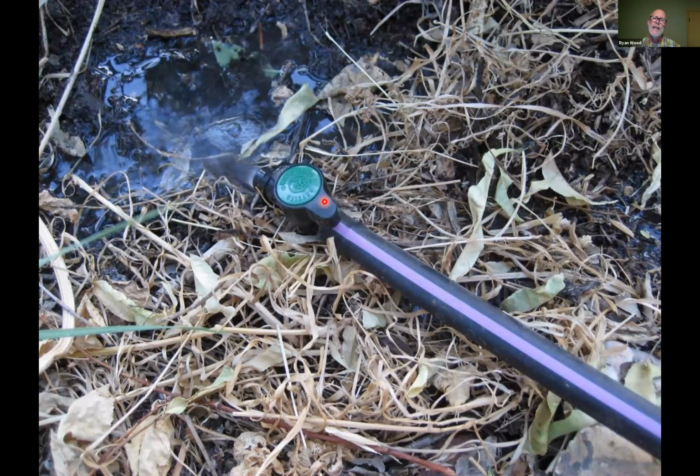And then depending on your laundry machine, you're going to have at least 4 to 12 outlets. It's going to depend on how big a drain hose you have on your washing machine. For example, if it's a 1 inch diameter hose coming off your washing machine, you're going to want at least six half inch outlets, because if you do the math on the inside diameter, those 6 outlets are going to be the equivalent of a 1 inch diameter hose. We don't want to restrict the water. That's the important part.